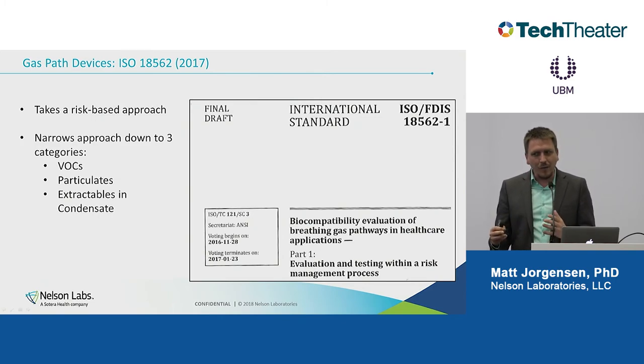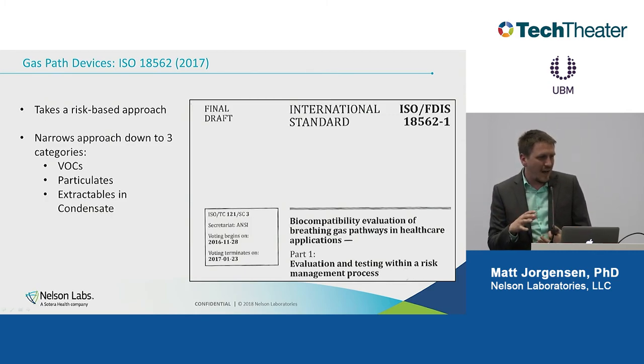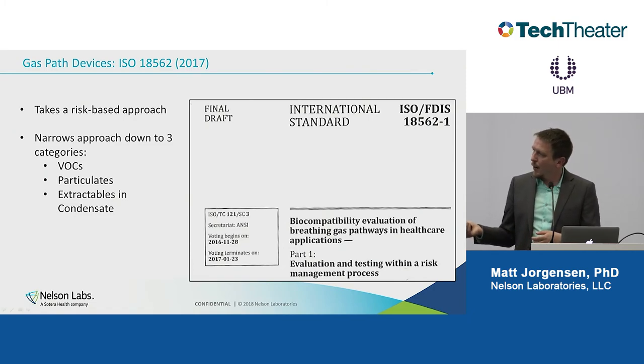Because if you're going to evaluate a gas path device, say something like an oxygen concentrator, it technically is external communicating with permanent contact to tissue, the lung tissue. And you go through and try to do a cytotox on that. If it has zeolite, which is the active ingredient in a lot of concentrators, it explodes when you touch it to water. So how do you test that?